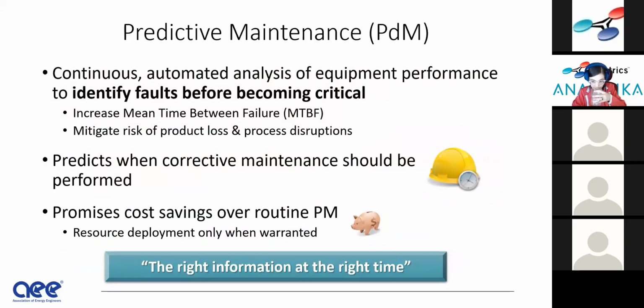So predictive maintenance, we talked about it just now. Continuous automated analysis of equipment performance, again, to identify faults and the root cause of those faults before they become critical. We're eliminating root cause here. In this way, we can increase plant availability, increase the mean time between failures, because we're catching more faults. We're implementing them, correcting them quicker, because we have more directed suggestions. It's not just, oh, this valve needs to be repaired. We know why, exactly what's going wrong, and data sufficiency helps with that, with root cause analysis. So we can tell them exactly the root cause of the failure.